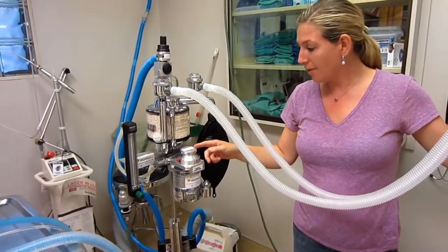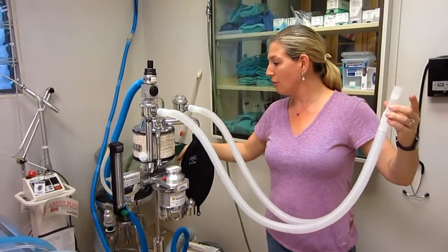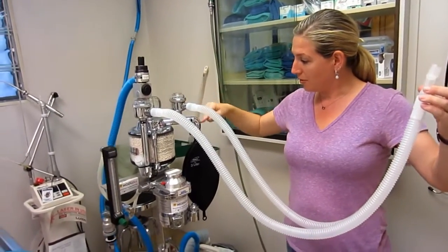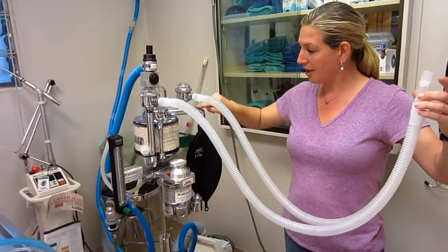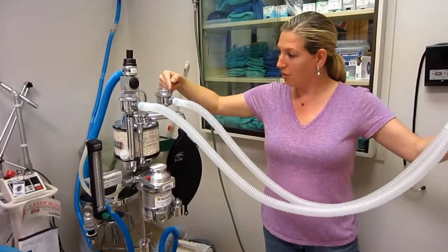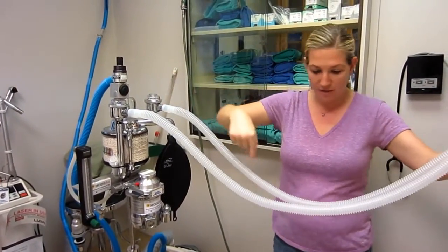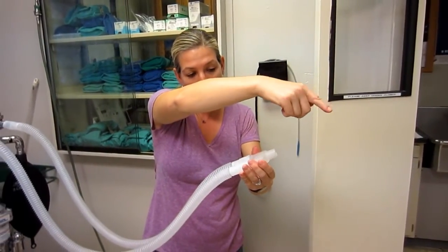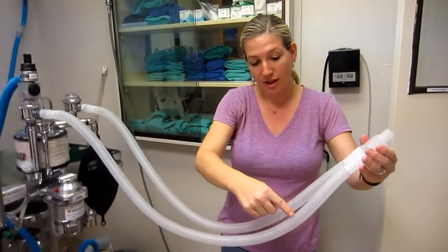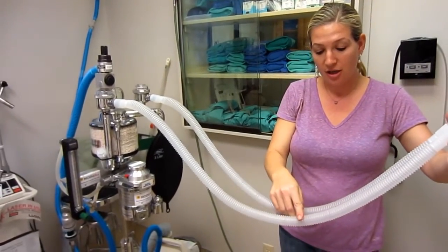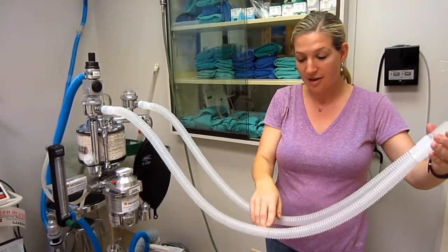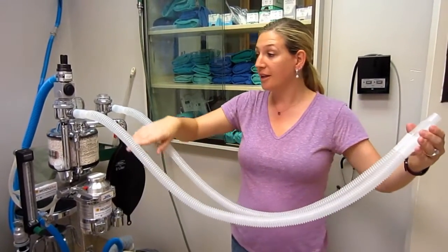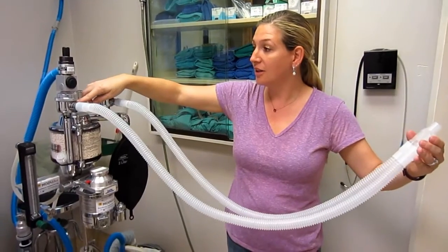The oxygen will pick up the isoflurane, come out the outlet port, go up to the inhalation valve. Some will come down into the reservoir bag, and then through the unidirectional inhalation valve down the inhalation tubing, delivered to our patient, exhaled, and what's exhaled is a little bit of oxygen, carbon dioxide, and anesthetic gas. It will come to our exhalation valve.